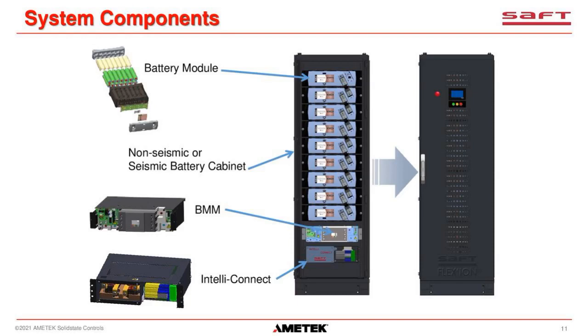And then the last thing in the cabinet is an IntelliConnect. This is what the UPS connects to. It is a contactor in parallel with a diode. So this battery was designed so that you don't have to have any communication with the UPS to use this lithium battery. In our application, we do communicate with it, so this isn't necessarily required for us, but the IntelliConnect contactor opens to prevent discharging or to prevent charging once the float voltage has been met. So if this contactor is open, you shouldn't be able to charge the battery. But since there is a diode in parallel with it, discharging is always available to the UPS.